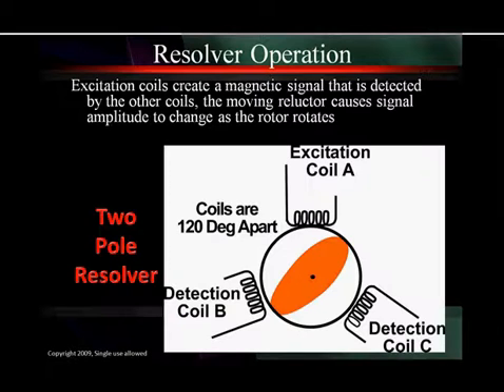Let's take a look at this up close. We have an excitation coil called coil A. It creates a magnetic field that is then detected by the other coils. The moving reluctor causes the signal amplitude to change as the rotor rotates.